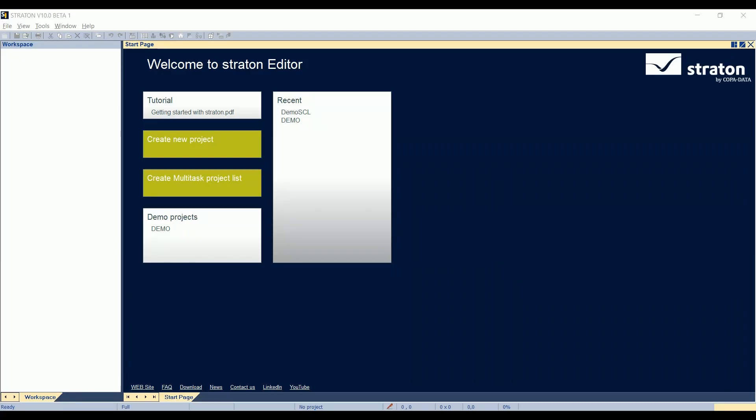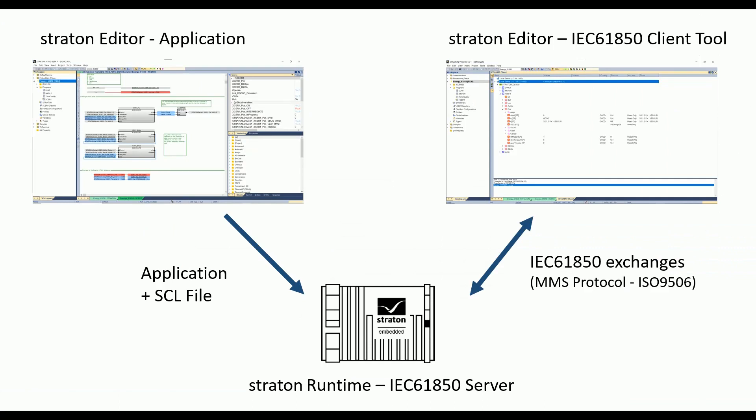Hello, in this video I will show you how to create an IEC 61850 server with Straton. We will use the demo application installed with the editor, set up an 850 server which will run on a Straton runtime hosted on a Raspberry, and finally use the 850 client tool installed with Straton to check that the communication is working as expected.